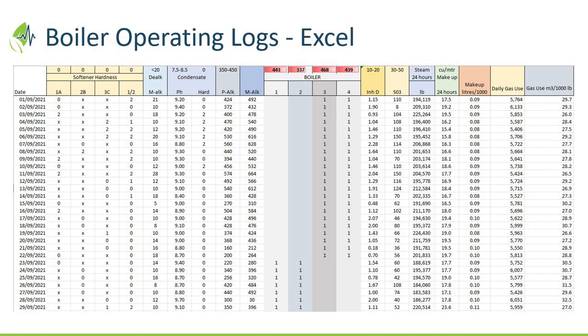How interesting is that? What do the high points mean? What do the low points mean? And somewhere in this 12-month period that's tracked here, those linkageless controls got installed. Again, this has just run the last few days to show all of us what's possible. But somewhere in there, there's a story coming up. You can see it's fairly tight, the blue points on the left-hand side. It gets much more scattered in the middle. Somewhere in there, the linkageless controls went in.